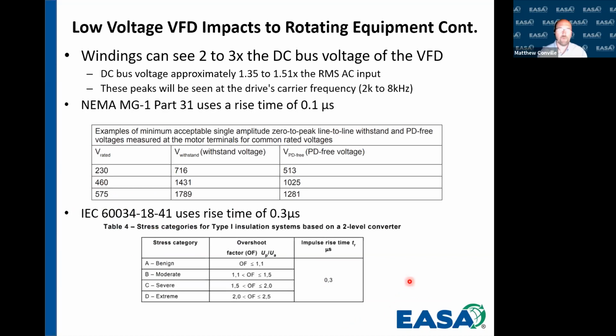So let's talk about what happens with windings. I talked to you about the fact that windings can see 2 to 3 times the DC bus voltage of the VFD. And this DC bus voltage is somewhere between 1.35 to 1.51 times the RMS AC input. And these peaks are going to be seen at the drive's carrier frequency, which is usually somewhere in the ballpark of about 2 to 8 kilohertz. So as an example, if we have a 480 volt AC input, we could have upwards somewhere between 620 to 720 volts for our DC bus.